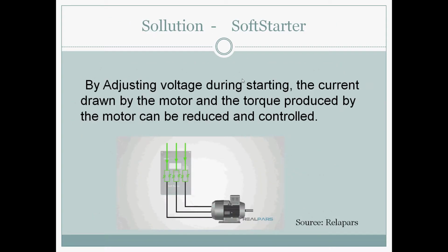To reduce that, the soft starter is here. By adjusting the voltage during starting, the current drawn by the motor and the torque produced by the motor can be reduced and controlled. Here you can see in the GIF image that a thyristor controller is given. It is ramping up the voltage slowly. So RPM is increasing while voltage and current are getting increased in a regular manner.